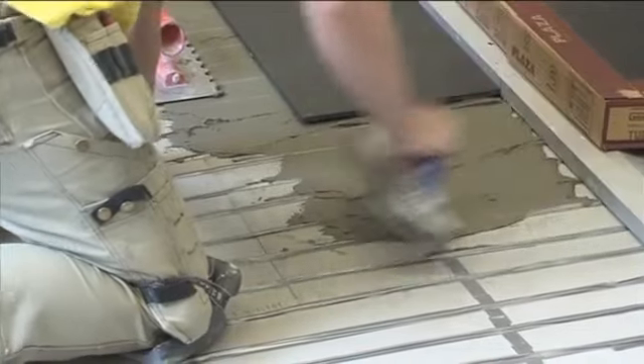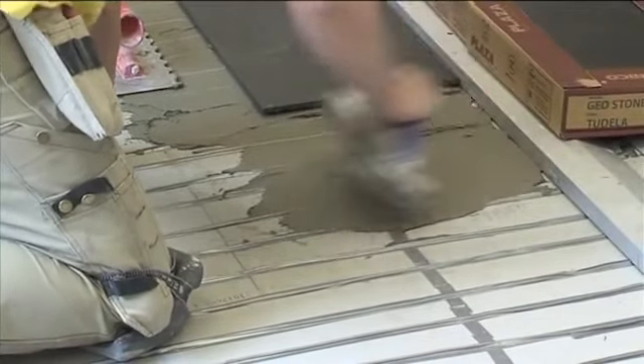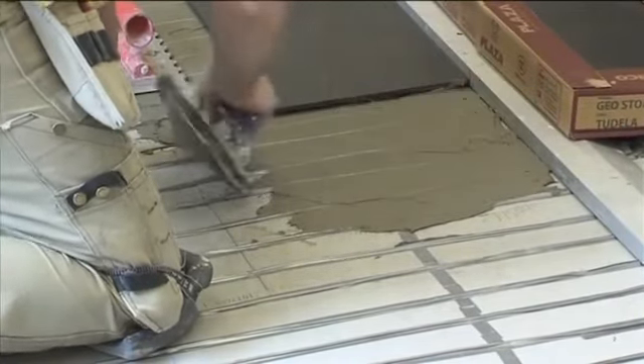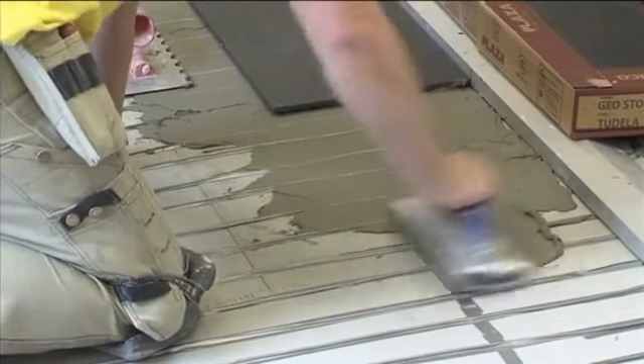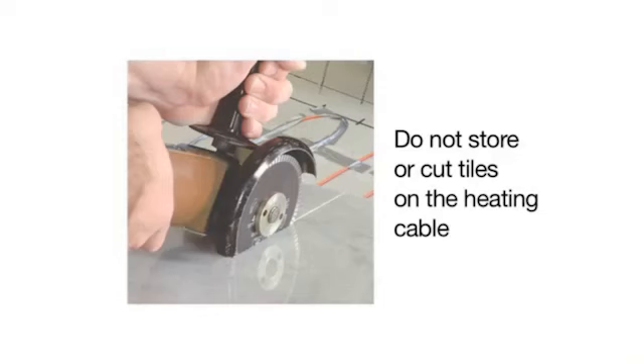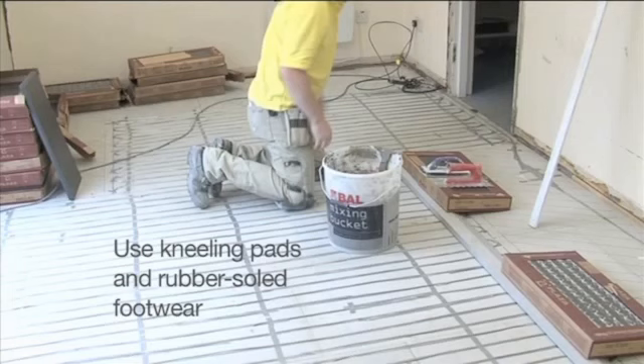The heating cable is robust, however care must be taken not to damage it during tiling. Use a piece of carpet or thick cardboard as a protective layer, or use a kneeling board to prevent damage to the heating cable from footwear or knees during the tiling process. Do not store or cut tiles on the heating cable. Use kneeling pads and rubber-soled footwear.